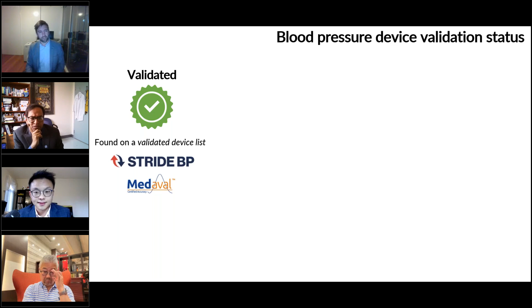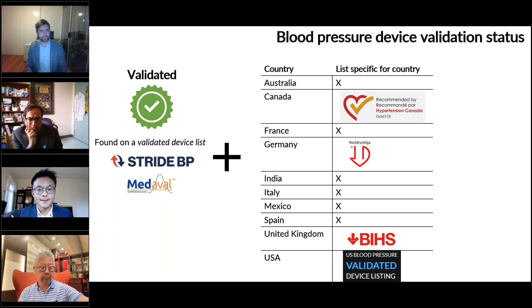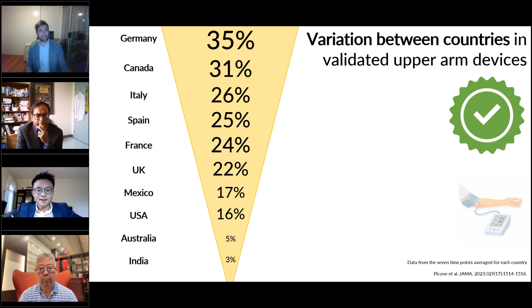to identify if devices were validated, because sometimes devices that are listed on one list, for example, Hypertension Canada, may not be found on the Stride and the Medaval databases, and that can just be due to regional differences or manufacturers submitting their information about validation status just to one listing. So what we found was that there were different levels of validation of upper arm cuff devices between different countries. So the highest percentage of validated devices was for Germany at 35%, and the lowest was Australia and India. And so this showed a bit of regional variation, but still, even Germany, that means that 65% of the devices were non-validated. So that's still the vast majority of devices on the bestseller lists being non-validated.